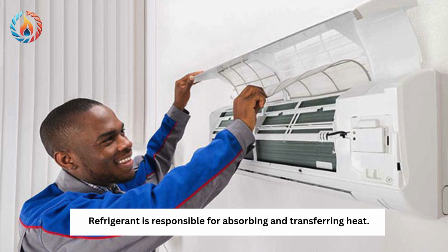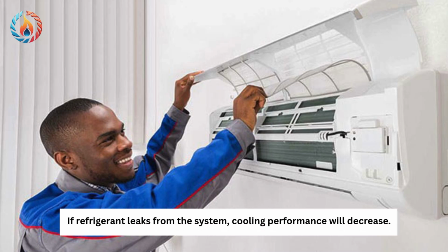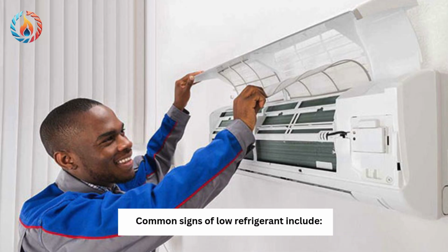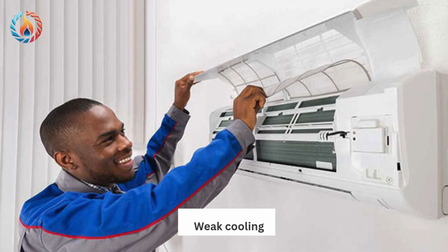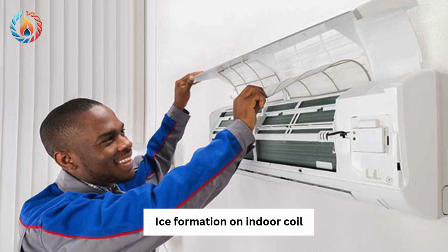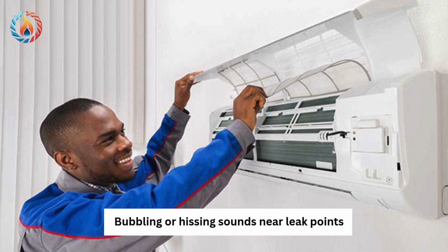3. Low refrigerant, gas, charge. Refrigerant is responsible for absorbing and transferring heat. If refrigerant leaks from the system, cooling performance will decrease. Common signs of low refrigerant include weak cooling, ice formation on indoor coil, longer running times, reduced airflow temperature, bubbling or hissing sounds near leak points.